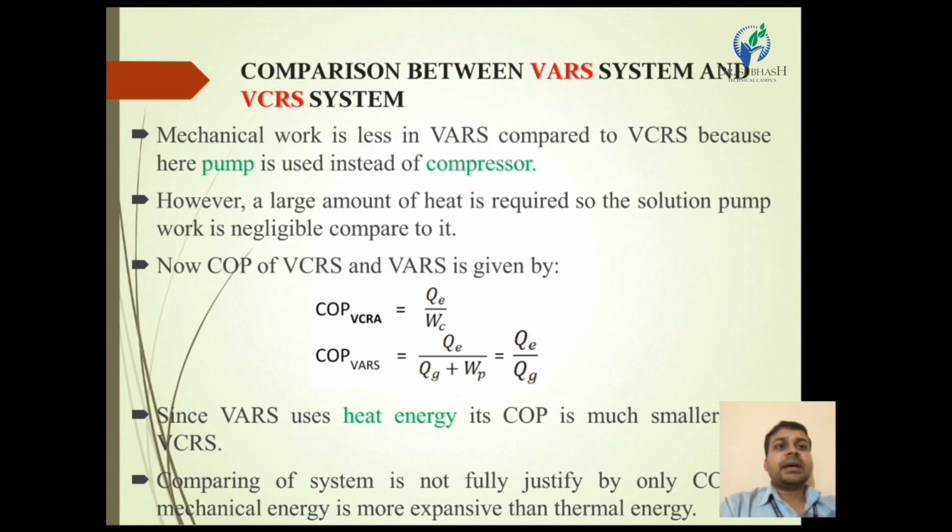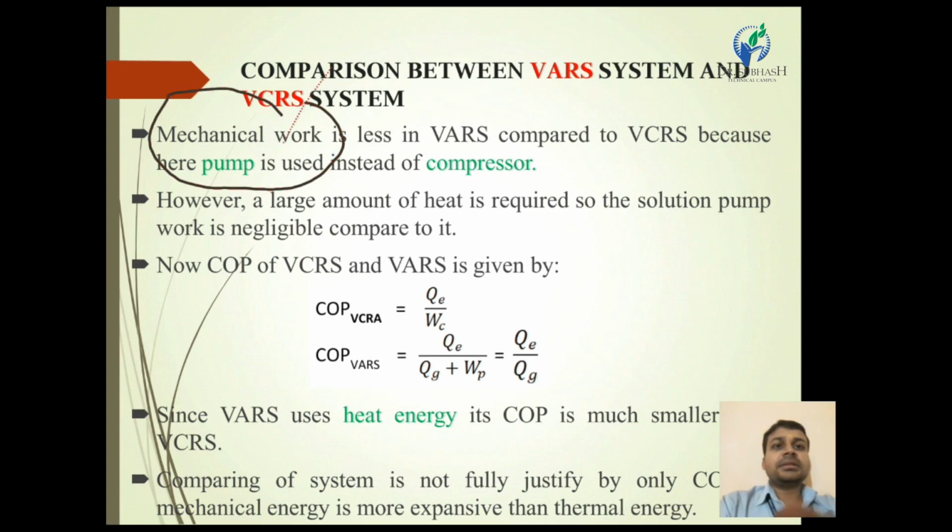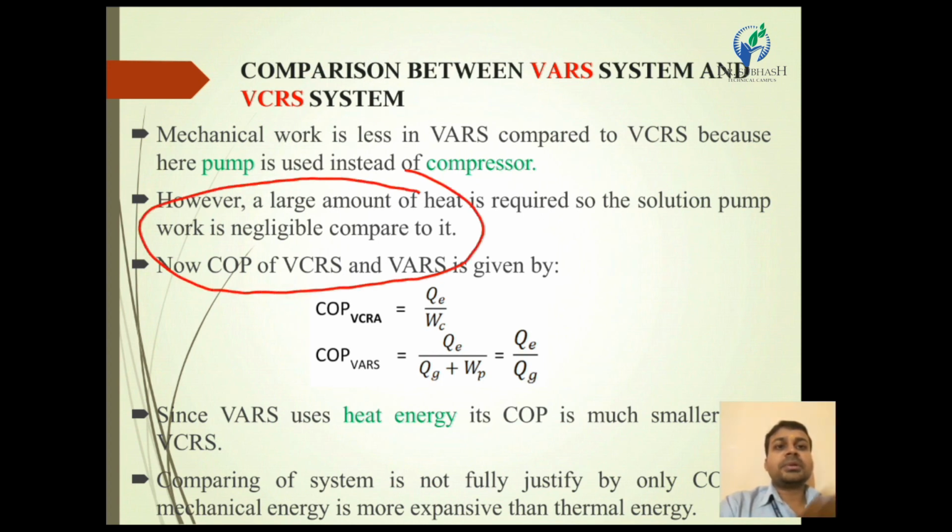Comparison between the VAR system and the VCR system. The VCR system requires mechanical work, while the VAR system requires rejected heat from some other place, so we can operate the generator and run the system. However, a large amount of heat is required, and the solution pump work is negligible compared to it. We consider compressor work in a VCR system and pump work in a VAR system, but the pump work uses very little power compared to the VCR system.